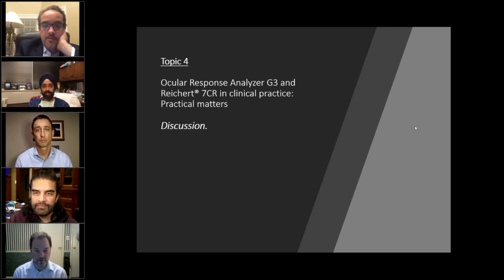This gets into the waveform score issue, which I know the other panelists have opinions on and experience with. My first suggestion would be, whenever the waveform score is low, question the accuracy, make another measurement, make a couple extra measurements. The waveform score is a signal quality from 0 to 10. I think the recommendation for the manufacturers, once you start getting down below 6, you have to start considering that perhaps the quality may not be as high as you like.